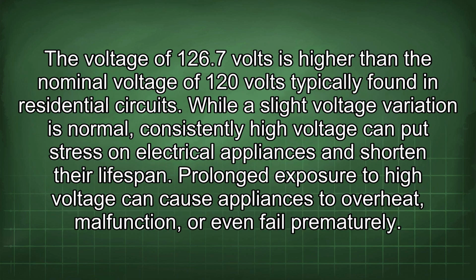The voltage of 126.7 volts is higher than the nominal voltage of 120 volts typically found in residential circuits. While a slight voltage variation is normal, consistently high voltage can put stress on electrical appliances and shorten their lifespan. Prolonged exposure to high voltage can cause appliances to overheat, malfunction, or even fail prematurely.